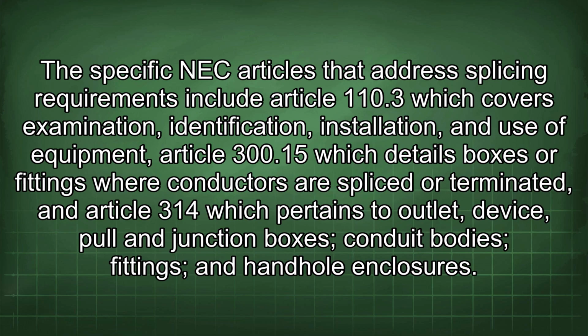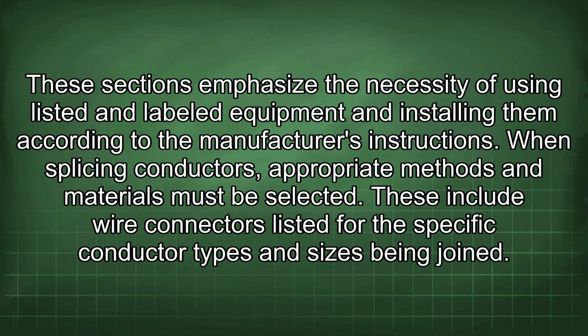systems. The specific NEC articles that address splicing requirements include Article 110.3, which covers examination, identification, installation, and use of equipment, Article 300.15, which details boxes or fittings where conductors are spliced or terminated, and Article 314, which pertains to outlet, device, pull and junction boxes, conduit bodies, fittings, and handhole enclosures. These sections emphasize the necessity of using listed and labeled equipment and installing them according to the manufacturer's instructions.